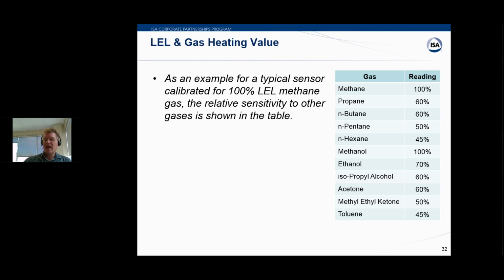So I did mention gas specificity and how methane is the most common gas. The reason I mention this is because we typically calibrate for methane, but if it's likely that you have hydrogen or propane or some other gas as the predominant gas in your facility, you either have to calibrate for that gas, or you'll have to make a correction factor to adjust basically for the heating value. So this table here just shows how different it could be, right? So 60% propane is the equivalent to a 100% methane reading.